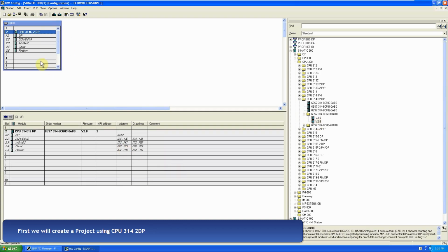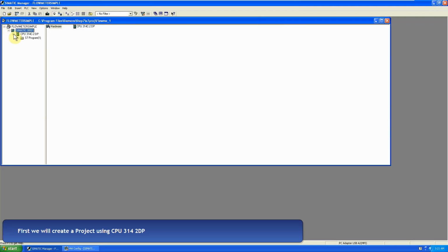The channel 0 analog input address is PIW752. Now, to configure the analog channel 0 as current input, we have to open the CPU properties and go to the inputs. Here we can change channel 0 to current input.